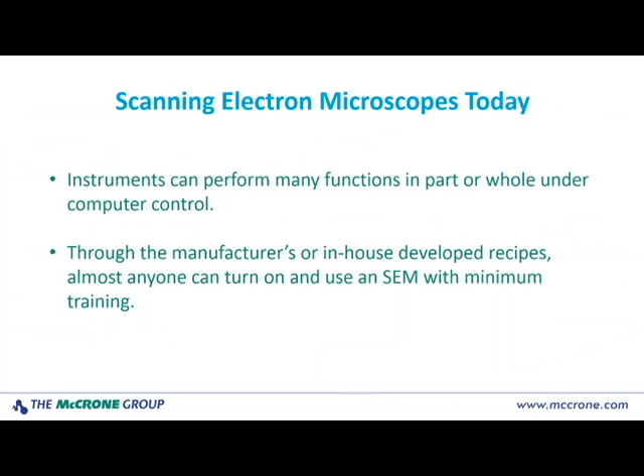In today's instruments many of the functions that are being performed can be done in part or in whole under computer control. This is enabled because the manufacturers have supplied a number of what they call recipes with the software and the instruments. These recipes, if you click on them, will set up the instrument for certain conditions like the column accelerating voltage, the spot size, the current and the working distance. Everything is already pre-programmed for you. So with the advent of recipes, and these can also be developed in-house, just about anybody can learn to turn on an SEM and acquire information.